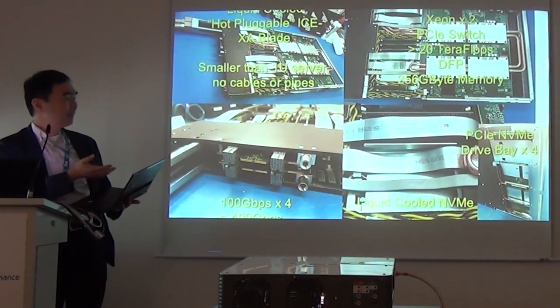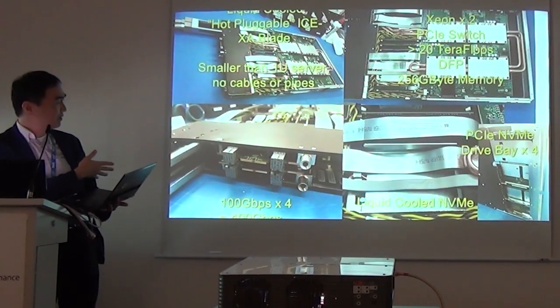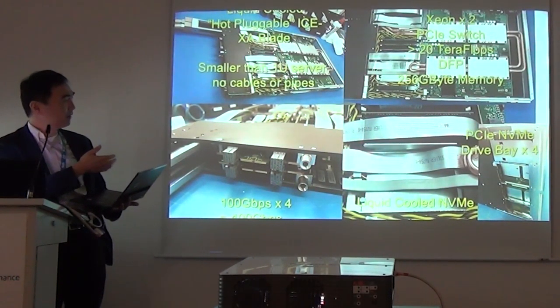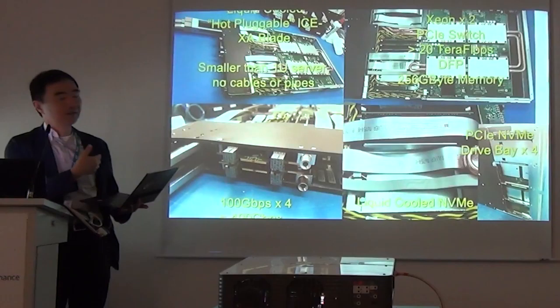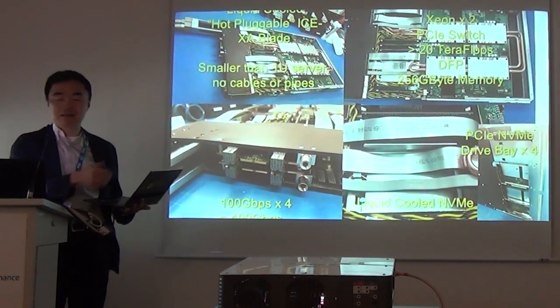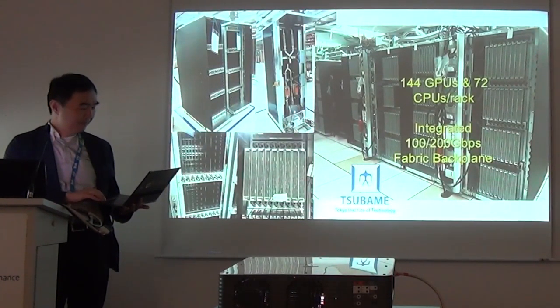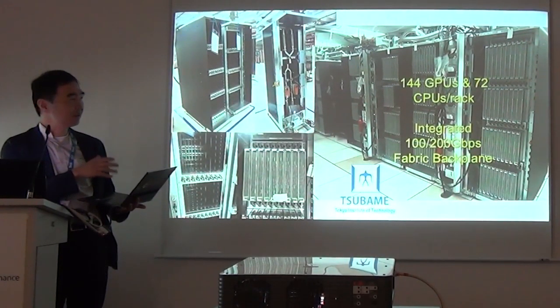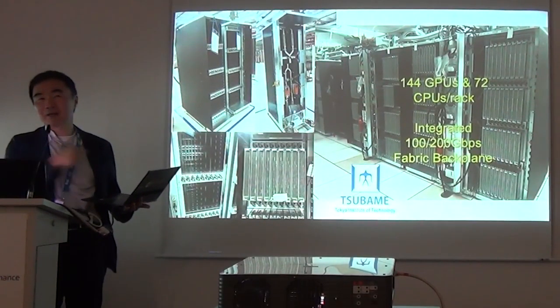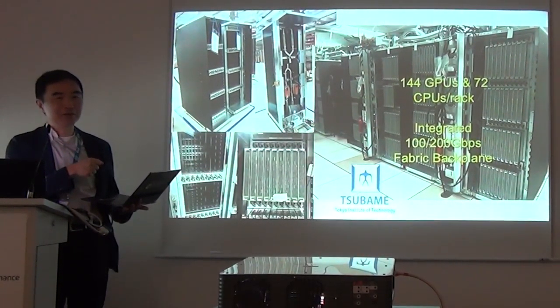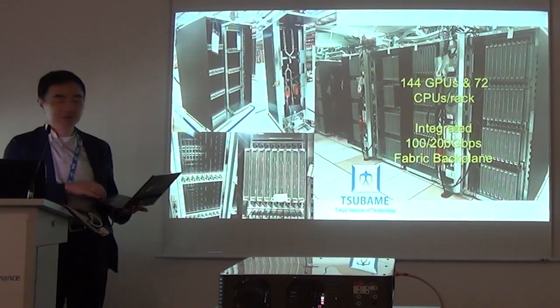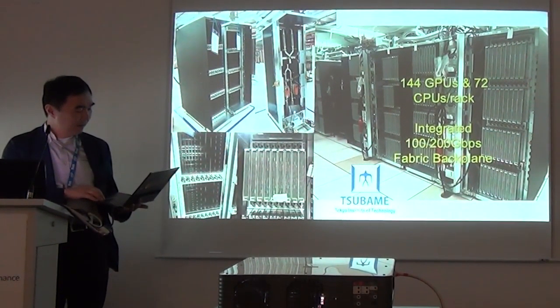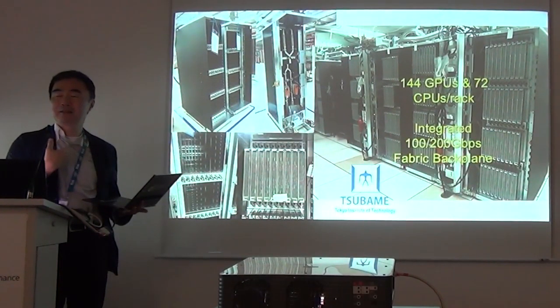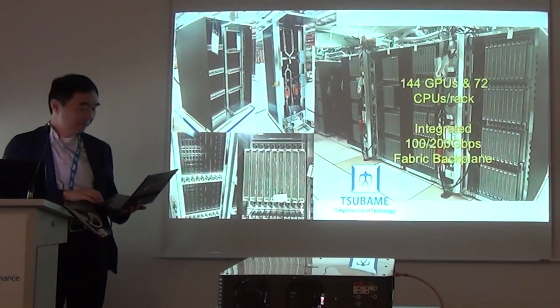It's a very tightly designed machine, co-designed with HPE. It's a pop-level blade with 400 gigabits of injection port from each blade with four GPUs. It's got very large memory and a very large NVMe capacity, and a very dense configuration. We've got 60 kilowatts per rack, but each of those blades can be hot plugged. There's no cabling at all, so the service is just instantaneous. Kudos to HPE for having a blade infrastructure and implementing our design in this manner.